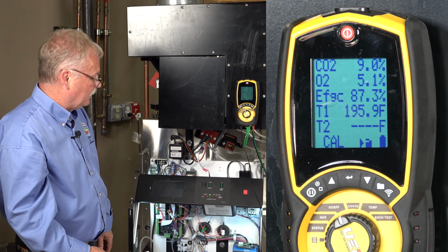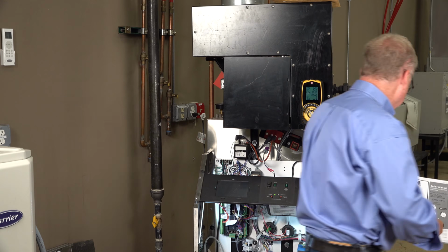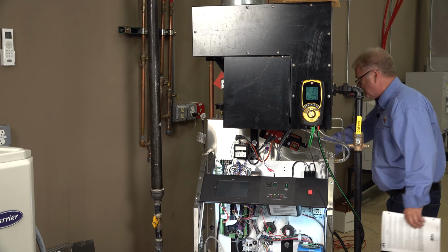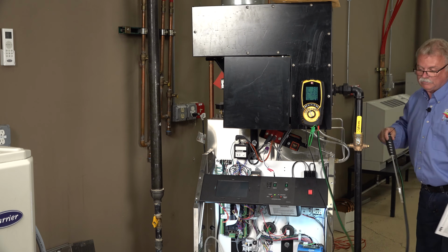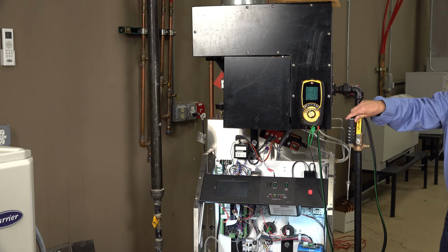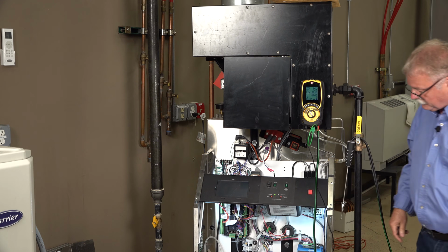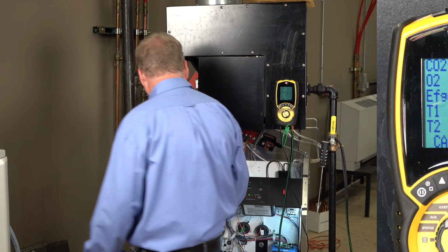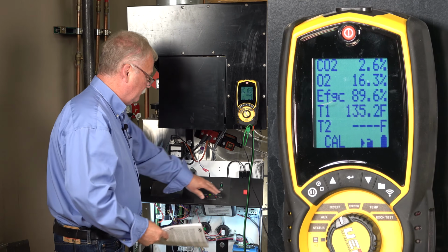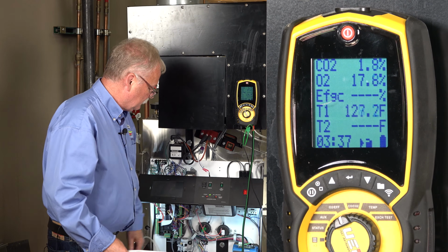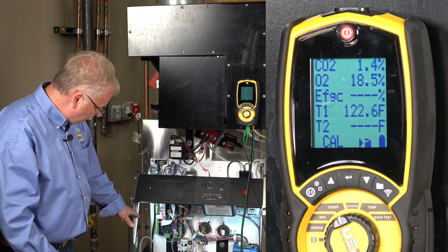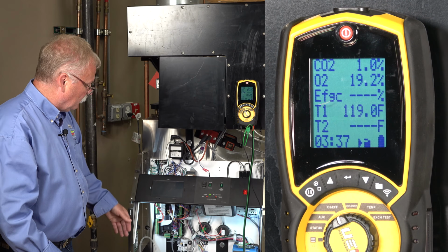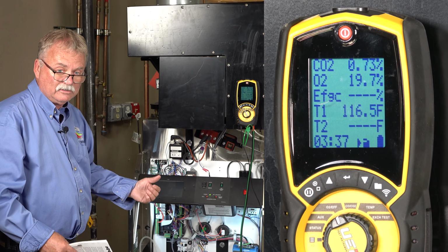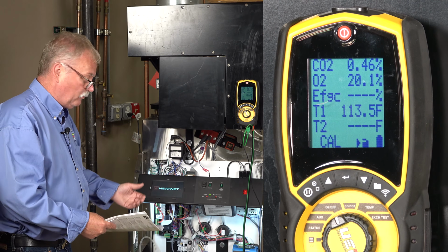I turned it off. I'm going to go pull my meter out because I want to start the boiler up again, just like it would be a natural fire. So I don't want my meter in there. I'm going to let the boiler basically fire itself. Calibration mode is off. The boiler now is going to come back up to a normal cycle at the set point and do it itself.